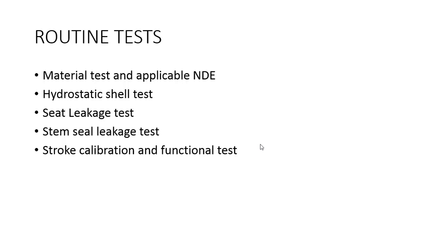Applicable NDE mostly used in the valve industry are as per B16.34, and they are liquid penetrant inspection, magnetic particle inspection, radiographic testing for the cast material, and if it is forged material, then ultrasonic testing is also considered.